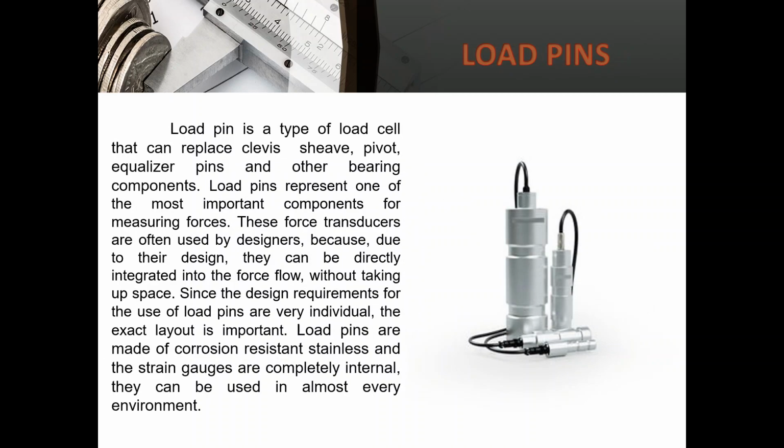The next one is the load pins. A load pin is a type of load cell that can replace clevis, sheave, pivot, equalizer pins, and other bearing components. Load pins can be used in cranes, winches, elevators, hoisting gear, sheaves, shackles, bearing blocks, and pivots.